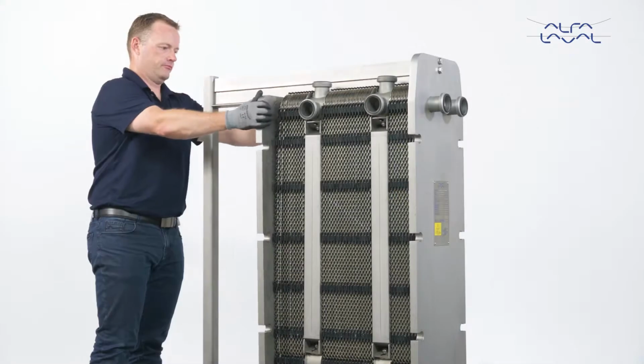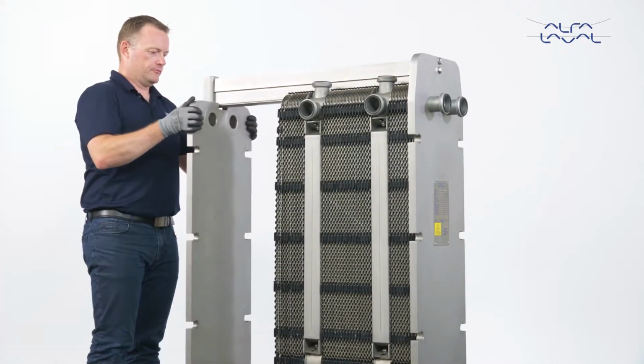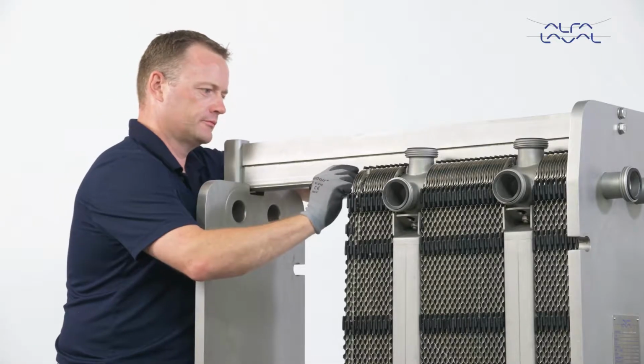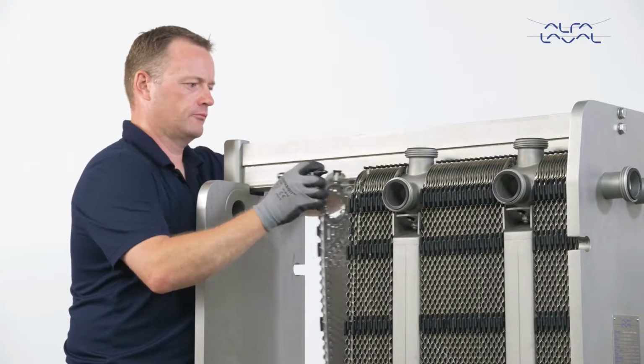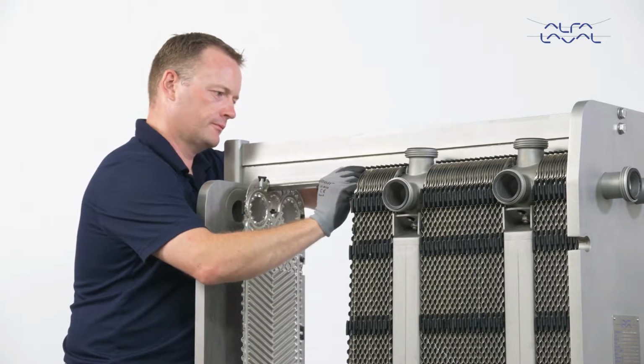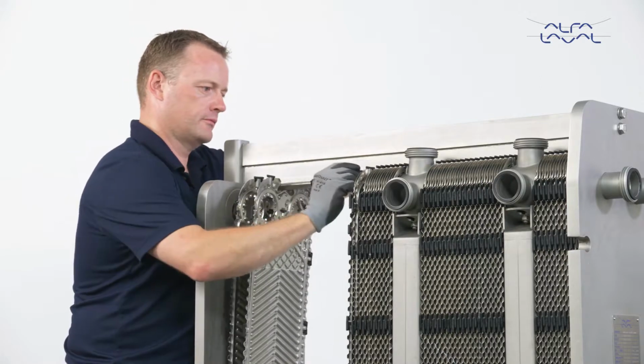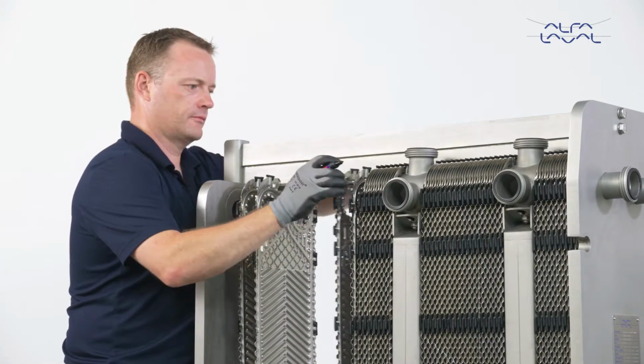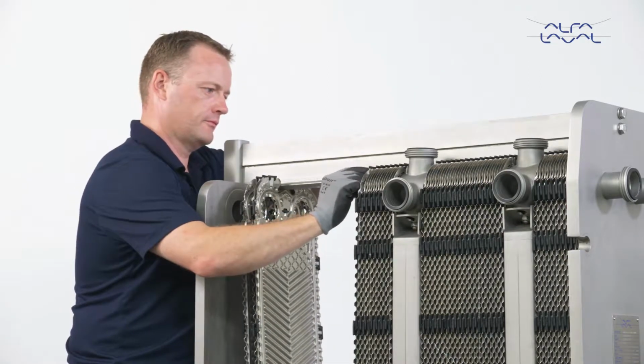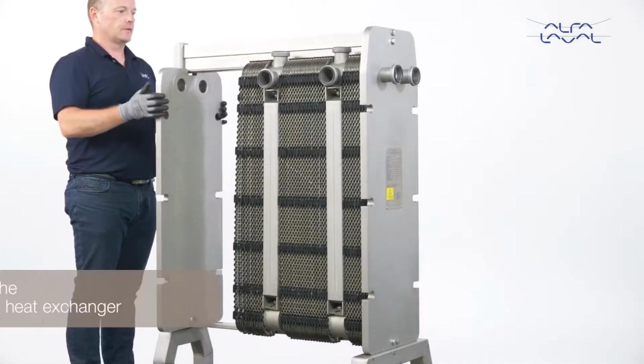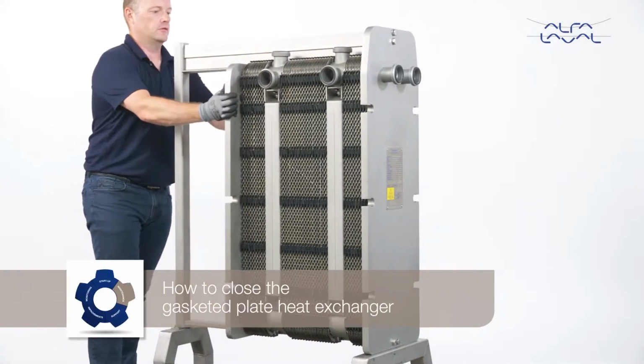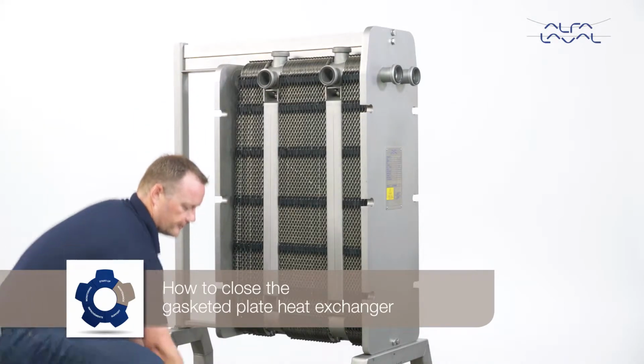Now, open the plate pack by sliding the pressure plate all the way back on the carrying bar. If you are only replacing gaskets, we recommend that you number the plates before removing them. Remember to use gloves when handling the plates. How to close the gasketed plate heat exchanger.